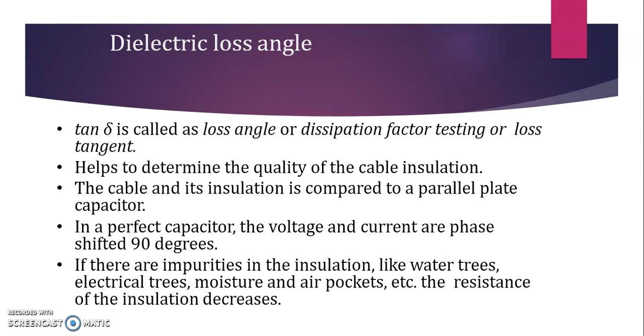Now under some circumstances, if some impurities are found in the insulation, maybe due to moisture, maybe due to some electrical disturbances, or maybe some air pockets, or maybe some dust, the resistance of the insulation will decrease. As this resistance decreases, this will result in a flow of resistive current through the insulation. So now your cable will no longer remain a perfect capacitor. Now that your cable is not a perfect capacitor, the current will not be leading the voltage by 90 degrees. It will be something less than 90 degrees.